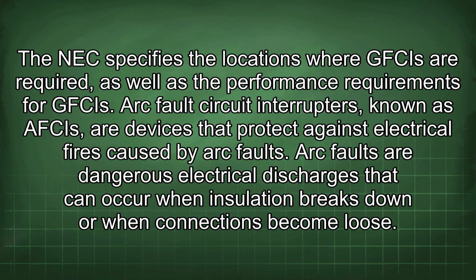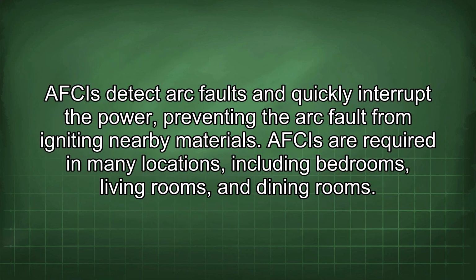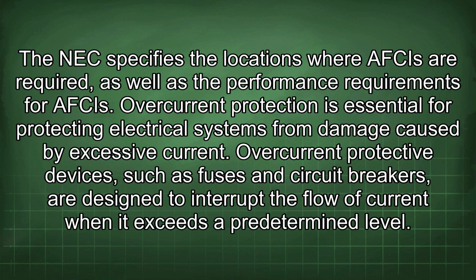Arc fault circuit interrupters, known as AFCIs, are devices that protect against electrical fires caused by arc faults. Arc faults are dangerous electrical discharges that can occur when insulation breaks down or when connections become loose. AFCIs detect arc faults and quickly interrupt the power, preventing the arc fault from igniting nearby materials. AFCIs are required in many locations, including bedrooms, living rooms, and dining rooms. The NEC specifies the locations where AFCIs are required, as well as the performance requirements for AFCIs.